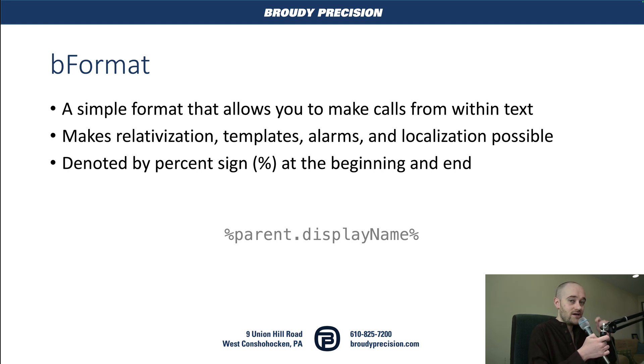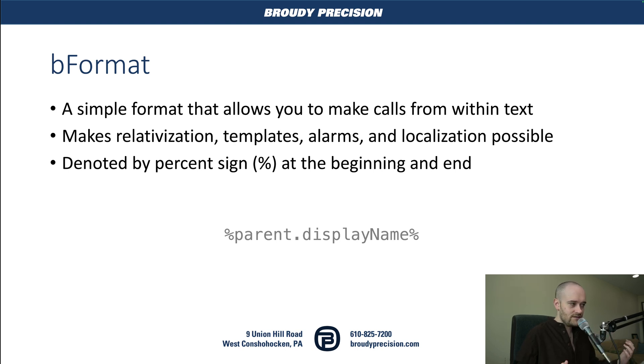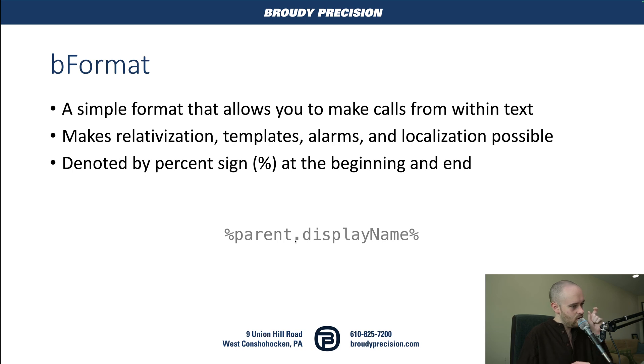B Format is a simple format that allows you to make calls to various parts of a Niagara station from just within a bit of string text. This is what makes relativization, PX's, templates, alarms, and localization all possible. You can tell it's B Format because of the percent sign at the beginning and the end, and we can also string these B Format calls together using a dot, like parent.displayName.